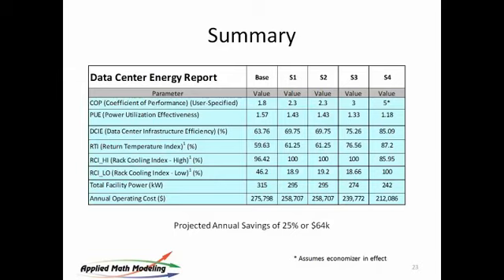So we're good there. And estimating cost savings to be 25%, I think that's conservative. I would say it's probably at least 30. In my experience, 30 is pretty easy to get out of these data centers. And you can look at this two ways. I realize we are making some assumptions about cost per year because we don't know the averages of these COP numbers. So you can make the assumption that this is an average and that these are fairly representative numbers. Or you can look at it as a percentage, which is kind of nice because a percentage is going to be applicable regardless of what the absolute numbers are. And you see here that we're able to show about 25% from the work we did on this data center alone.